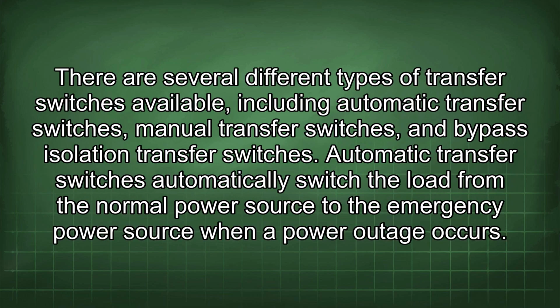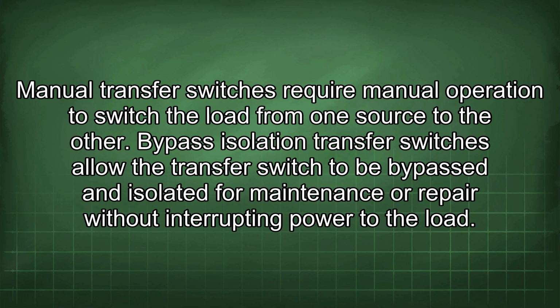There are several different types of transfer switches available, including automatic transfer switches, manual transfer switches, and bypass isolation transfer switches. Automatic transfer switches automatically switch the load from the normal power source to the emergency power source when a power outage occurs. Manual transfer switches require manual operation to switch the load from one source to the other. Bypass isolation transfer switches allow the transfer switch to be bypassed and isolated for maintenance or repair without interrupting power to the load.